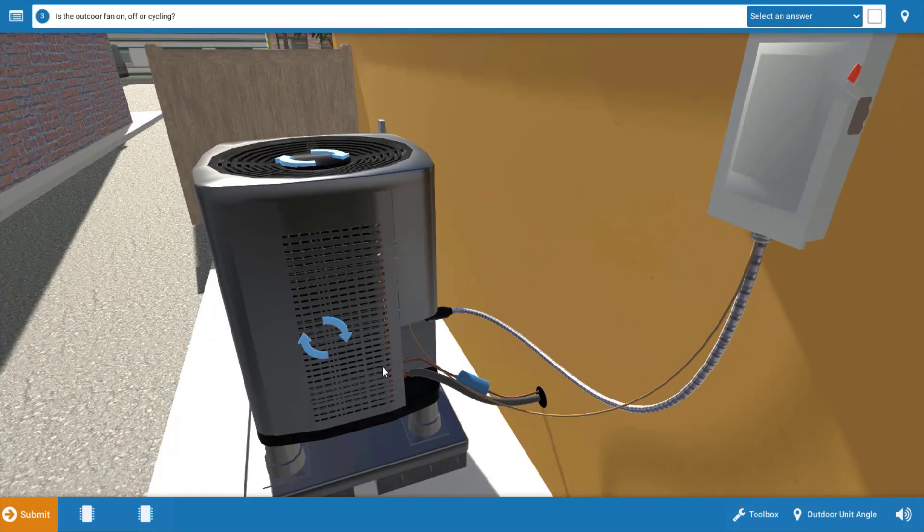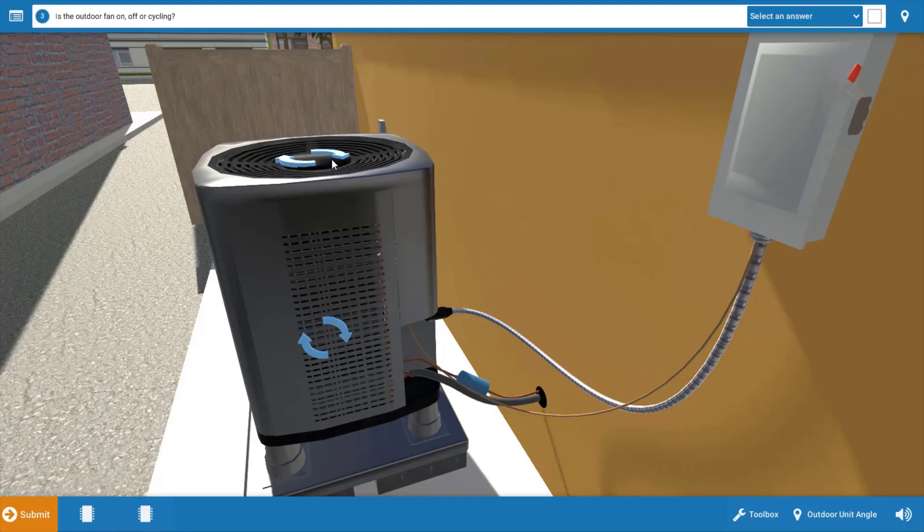And when we get to the outdoor unit, we can see that neither the compressor nor the condenser fan motor are running. Now that means both of these motors are de-energized.